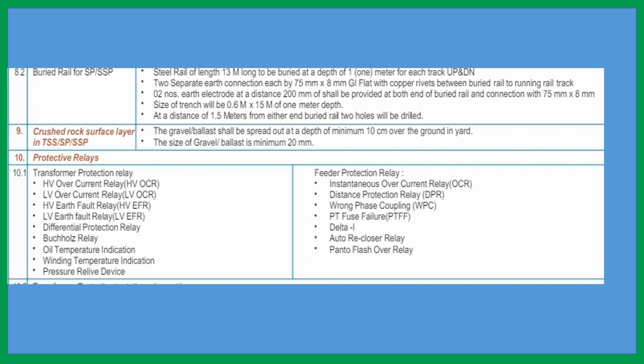Here all the relays will trip both sides of the transformer, except the 25 kV LV IDMT OCR and HV IDMT OCR. It will permit the overload of the power transformer. You are aware that a power transformer can give 200% overload. If it is 10 MVA, that means it can give 20 MVA for 5 minutes and 15 MVA for 15 minutes, if the capacity of the power transformer is 10 MVA.